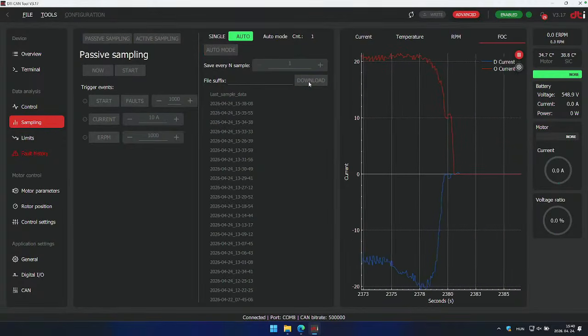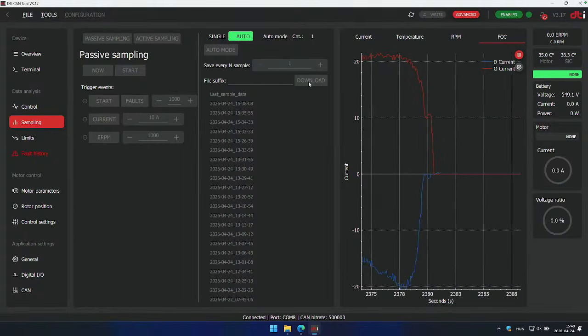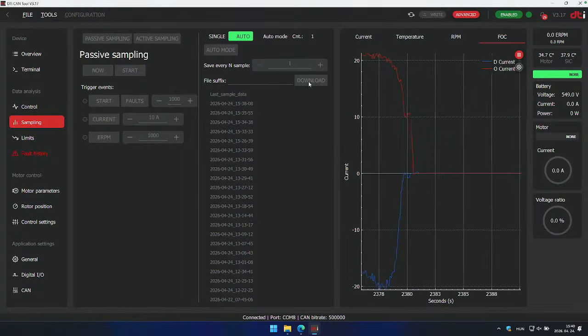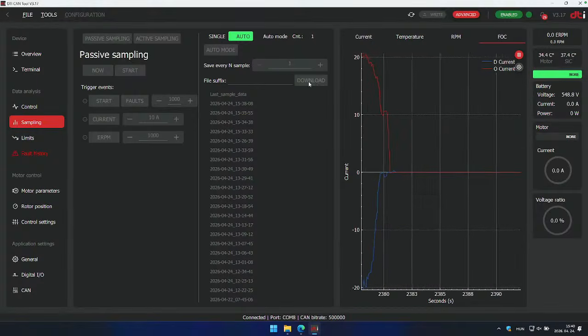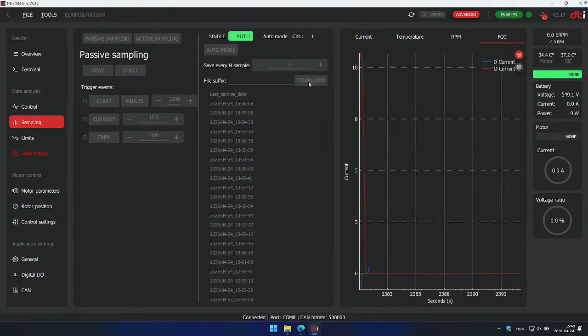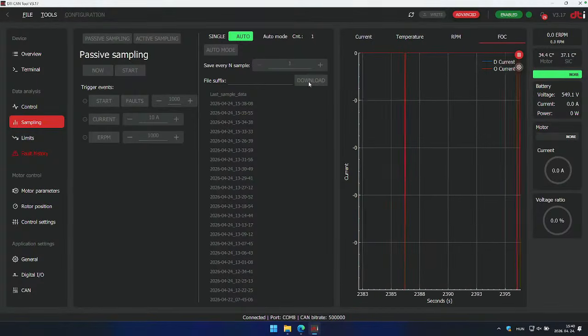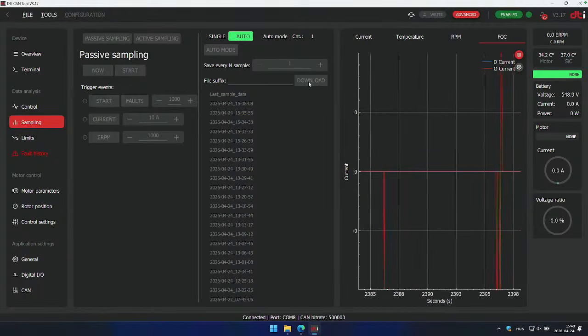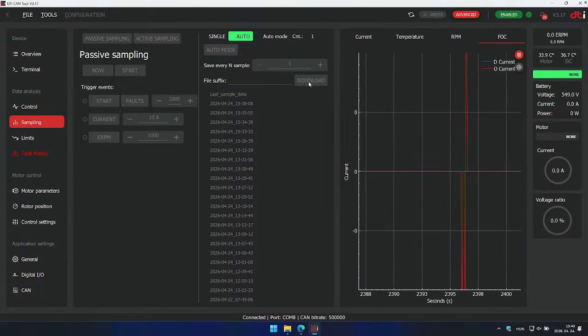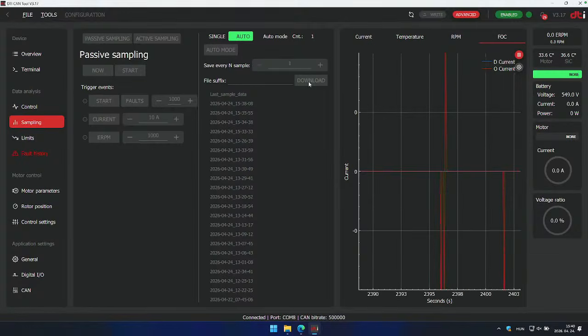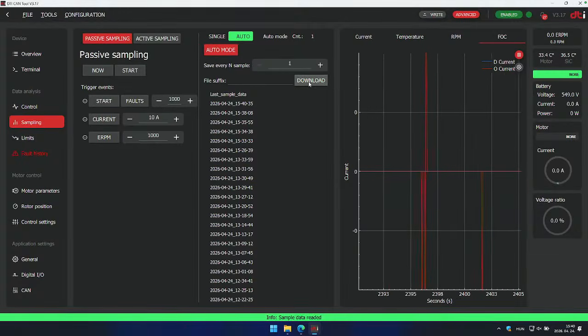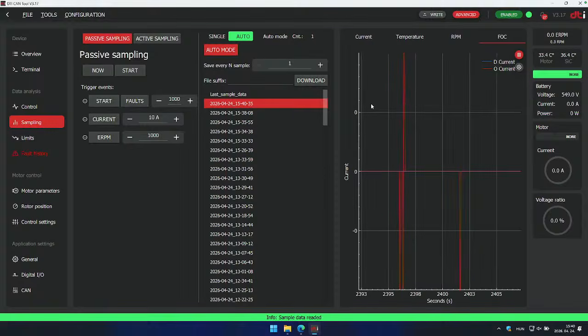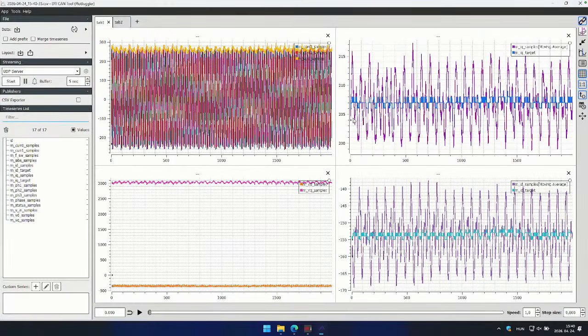I'd recommend going up to about 15,000, 17,000, 19,000 RPM, stopping at each point to take a sample and see what's happening — not jumping straight into the field weakening region, but increasing step by step and observing for oscillations, since field weakening is quite sensitive.